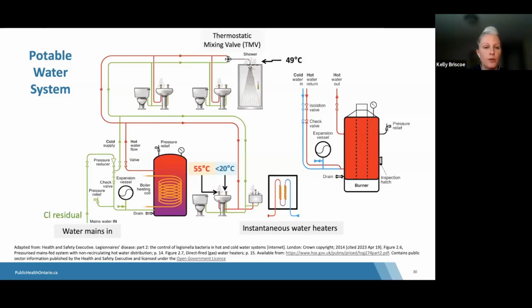So temperature is an important control measure and is a traditional means of preventing Legionella growth. For larger types of buildings, it's recommended to have hot water heater temperatures maintained above 60 degrees Celsius and have hot water temperatures at distal or endpoints exceed 55 degrees Celsius. Keeping hot water above 55 is a challenge due to scalding concerns, especially for those at an increased risk, such as children or the elderly. As many of you may know, under the Long-Term Care Homes Act, there is a requirement that the temperature of water serving resident units in long-term care homes must not exceed 49.